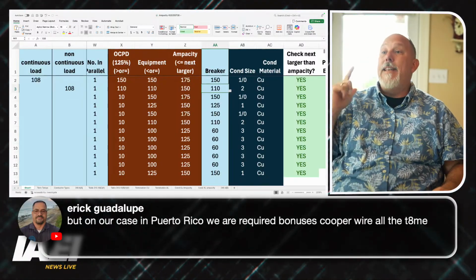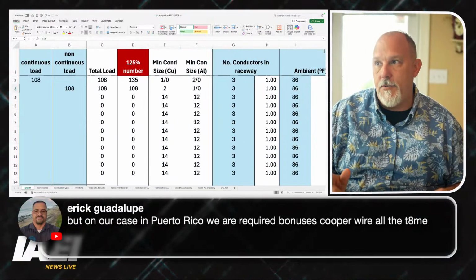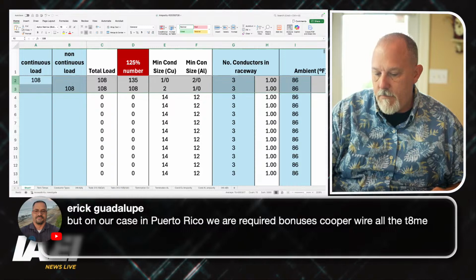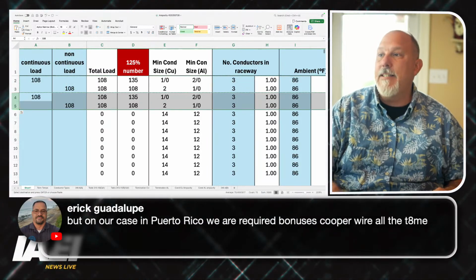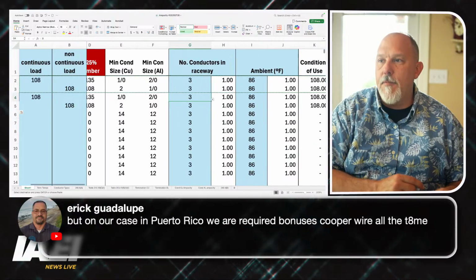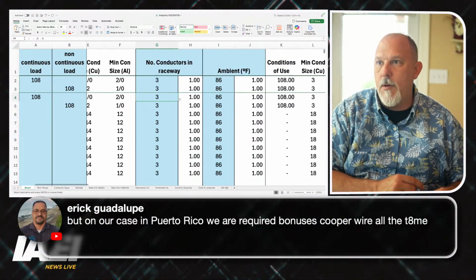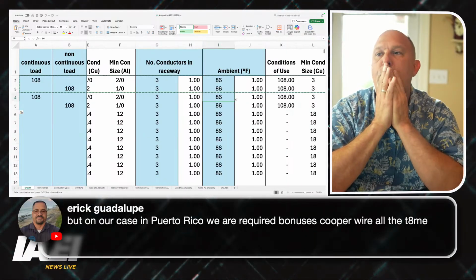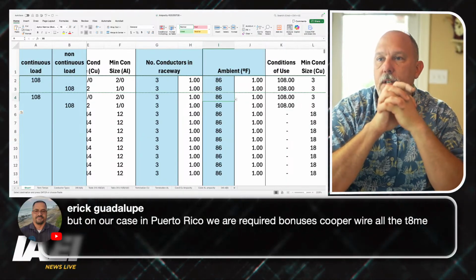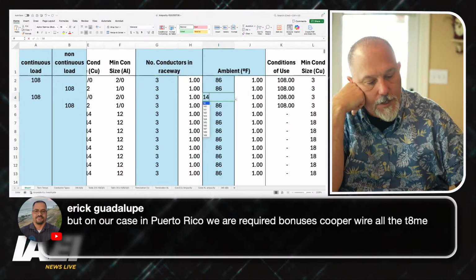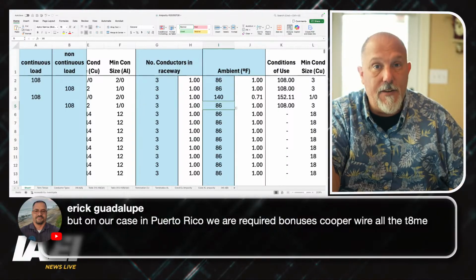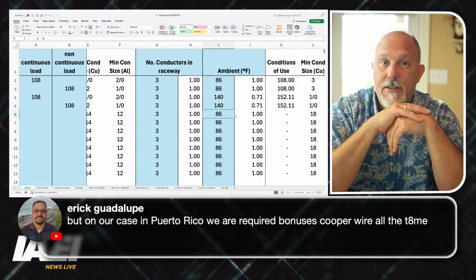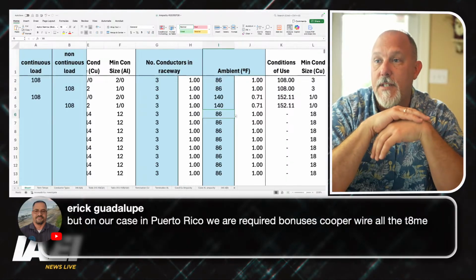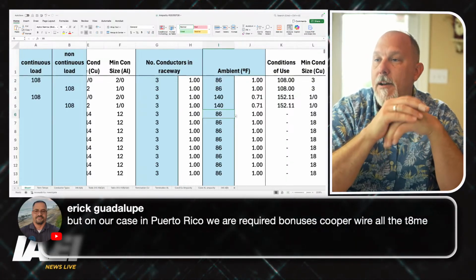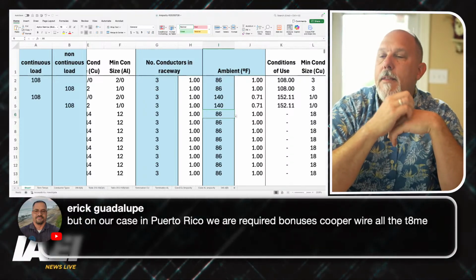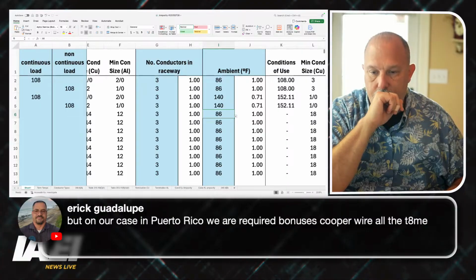All right, so now let's take the same 2 scenarios. I'm going to copy these, and we're going to change the conditions of use. We're going to leave 3 conductors in a raceway, but we're going to change the ambient. Let's say, for example, a good length of this is in the attic, and it's 140 degrees Fahrenheit. I use Fahrenheit because I don't know Celsius. I'd have to do a conversion somewhere, so I'm just doing the conversion for you. 140 degrees Fahrenheit. That means my multiplier on ampacity, I heard it click.